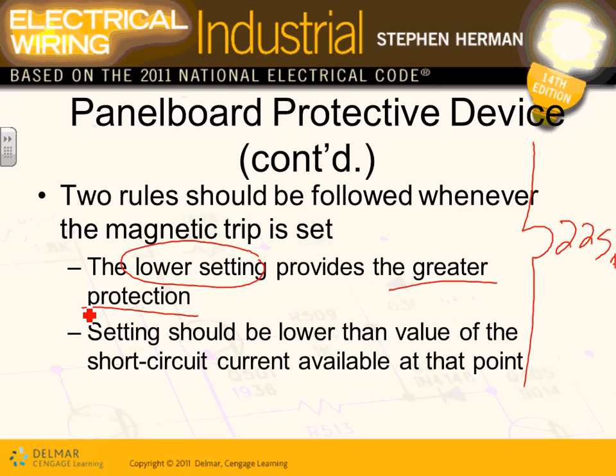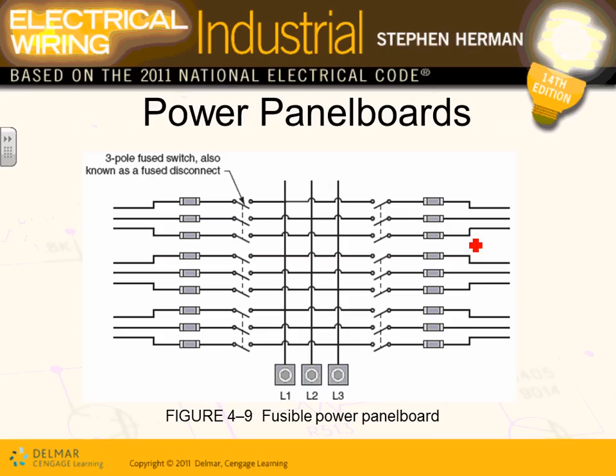But the lower the settings, time-wise, time and current, the lower the setting on the time and the current, the more protection you have. What's the drawback? The drawback, ladies and gentlemen, is miscoordination. The drawback is miscoordination, nuisance tripping.